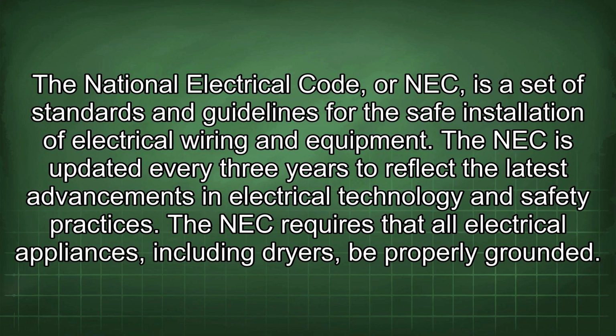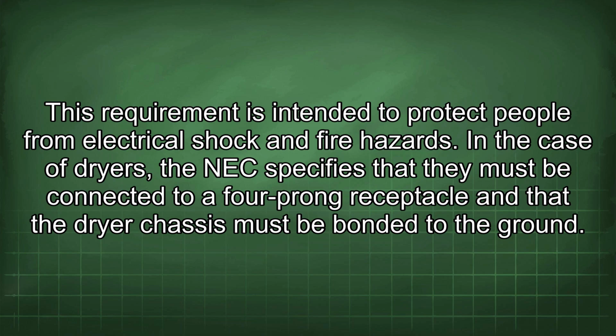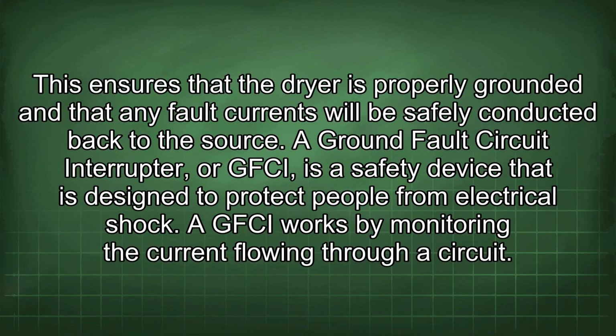The National Electrical Code, or NEC, is a set of standards and guidelines for the safe installation of electrical wiring and equipment. The NEC is updated every 3 years to reflect the latest advancements in electrical technology and safety practices. The NEC requires that all electrical appliances, including dryers, be properly grounded. This requirement is intended to protect people from electrical shock and fire hazards. In the case of dryers, the NEC specifies that they must be connected to a 4-prong receptacle and that the dryer chassis must be bonded to the ground. This ensures that the dryer is properly grounded and that any fault currents will be safely conducted back to the source.